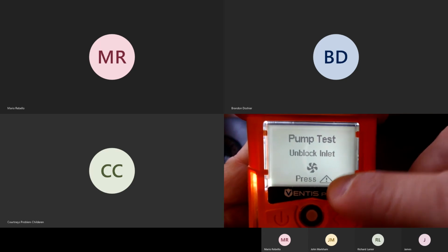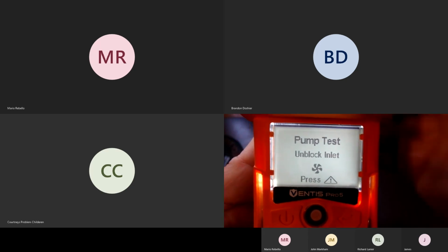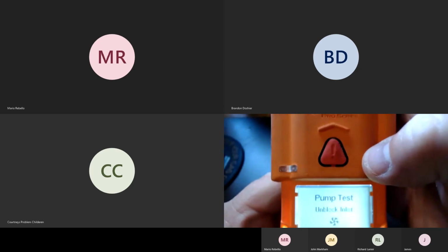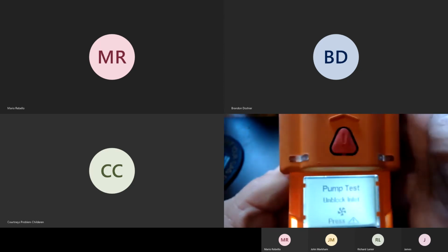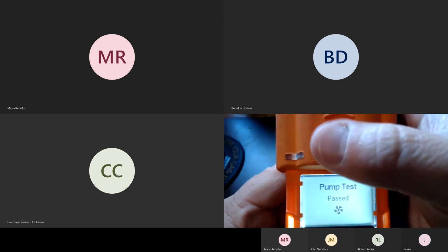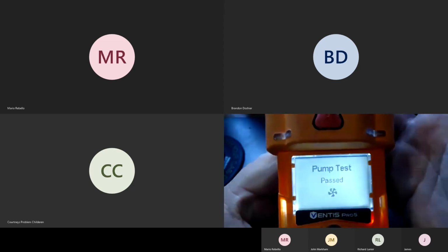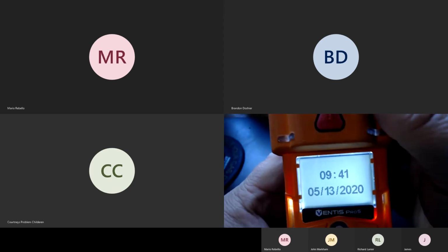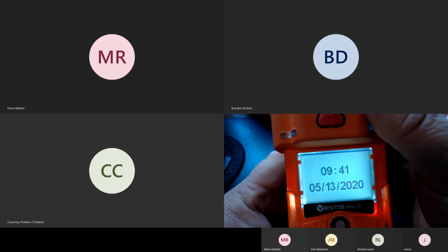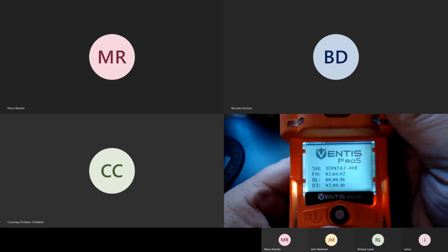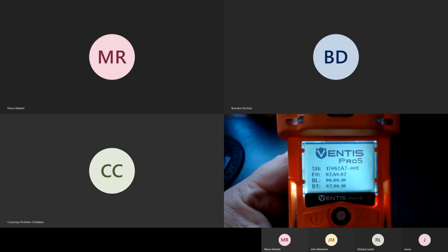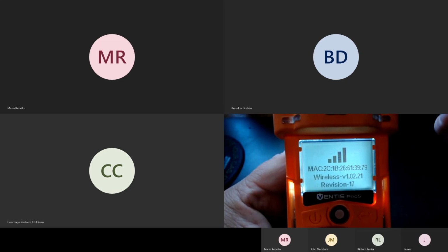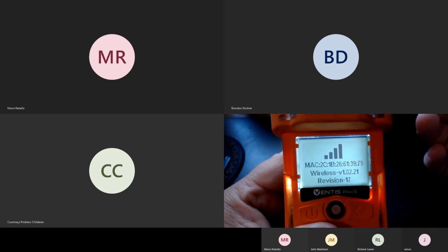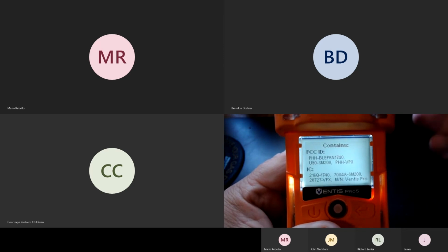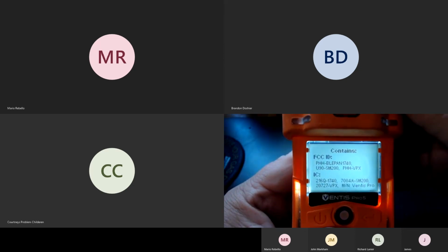Whenever it's done, it will come up and say press triangle. That's because it's telling you to press the panic button. Just give it a quick press. Don't press and hold. If you press and hold, it doesn't acknowledge it. Now, if you don't do the pump test, the instrument will not continue with startup. Then it will continue running through all of its startup displays, showing you the date of last calibration, the current date and time, all of the FCC IDs and everything else.